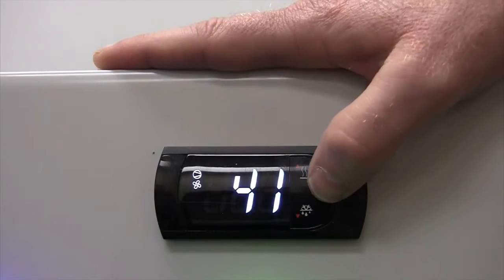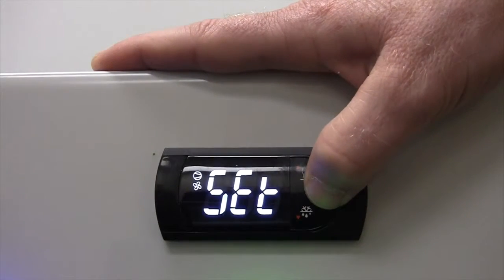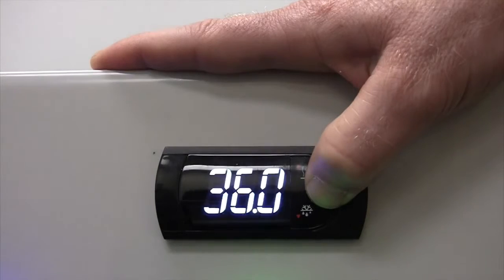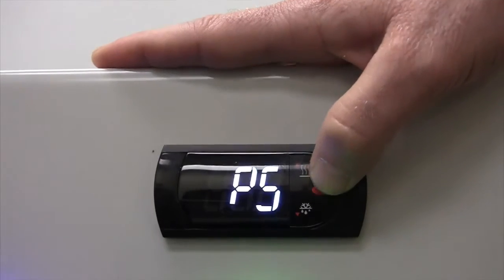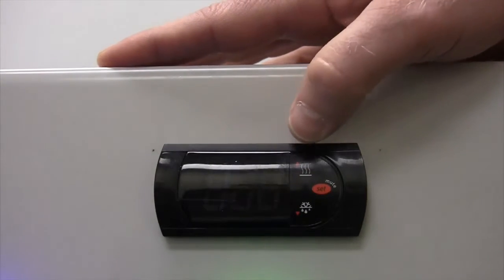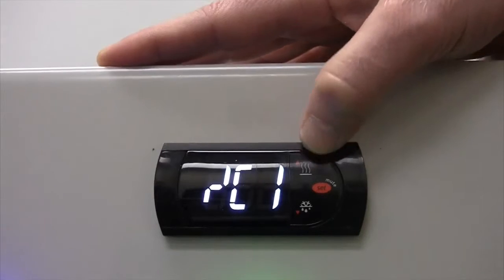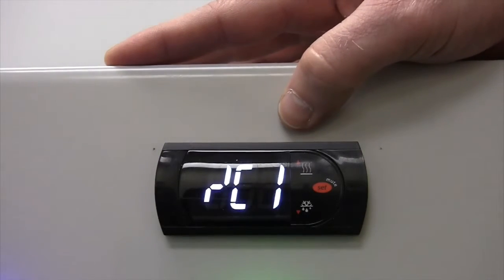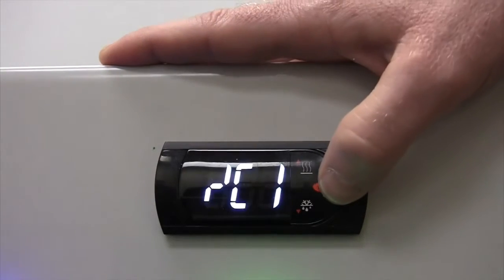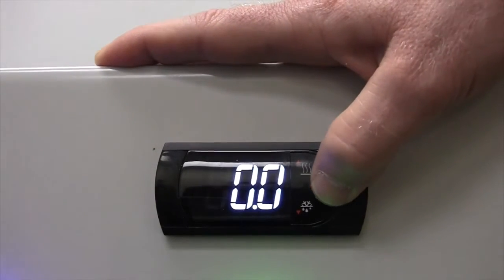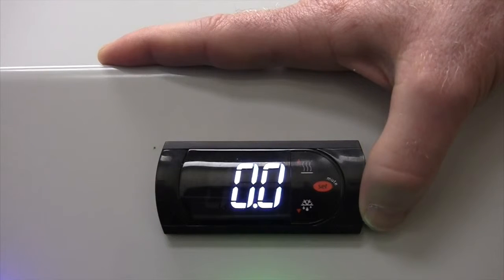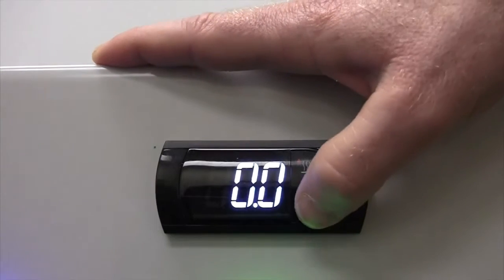To calibrate the electronic control, press and hold the set button. P5 will appear flashing in the display. Press the up button until rC1 appears in the display. Press and hold set.